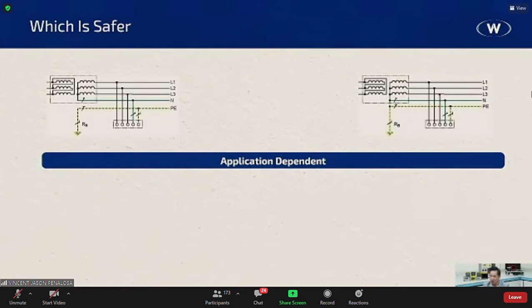However, how about in hospitals? How about in hospitals? Now, there is a little known fact that operating theaters, operating rooms for that matter, has to be on an ungrounded system. Why? Because in an ungrounded system, dependent on the leakage capacitance, in an event of a first fault, of an asymmetrical fault, right? Of an asymmetrical fault, just meaning one line to ground, the protective device will not open, right? Dependent on leakage capacitance. And in fact, this is already in the standards.